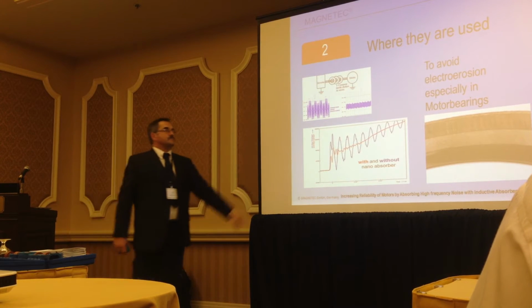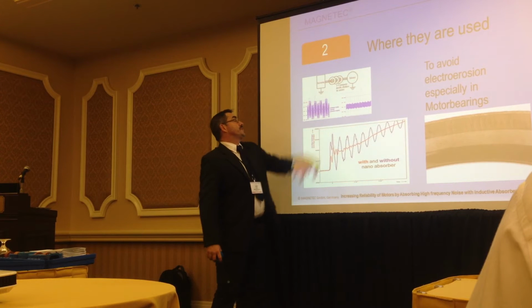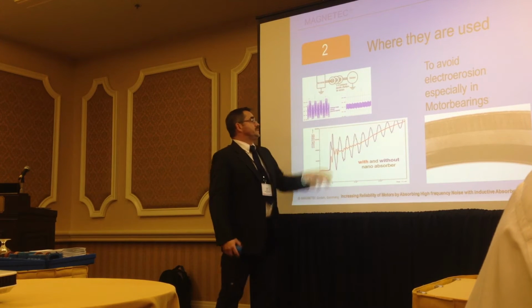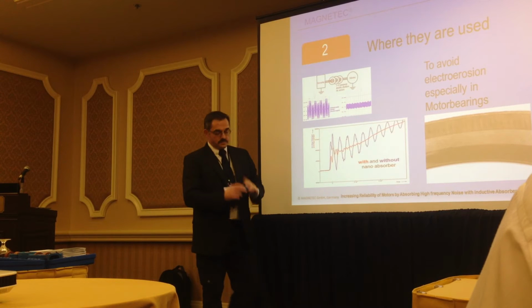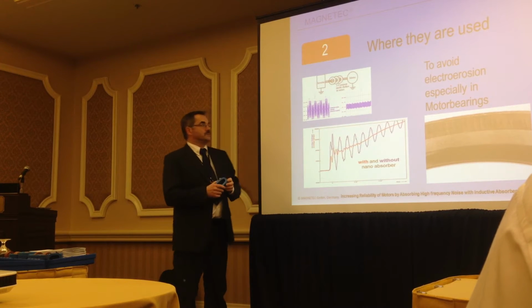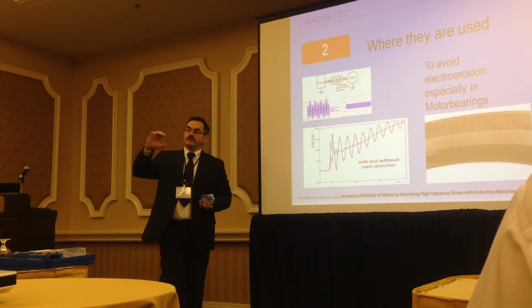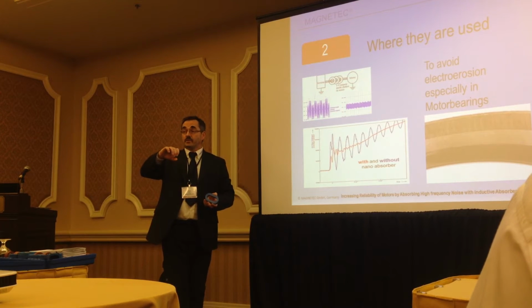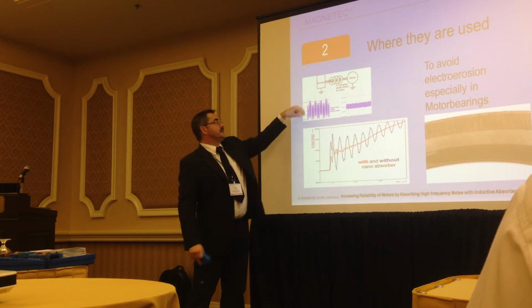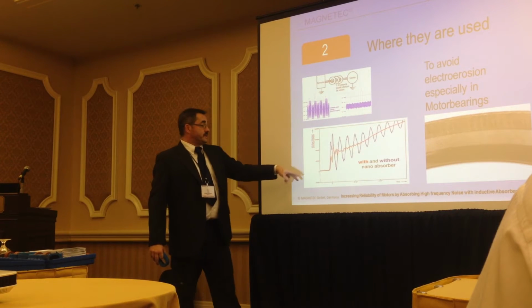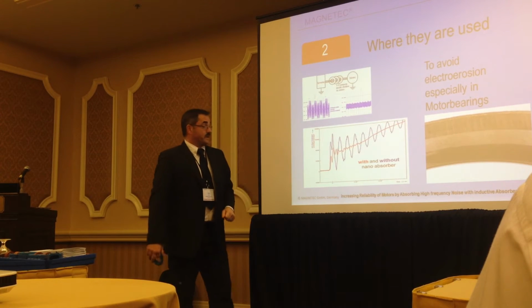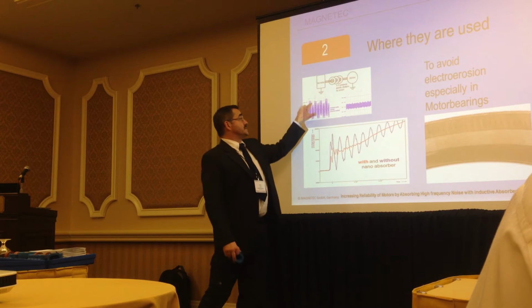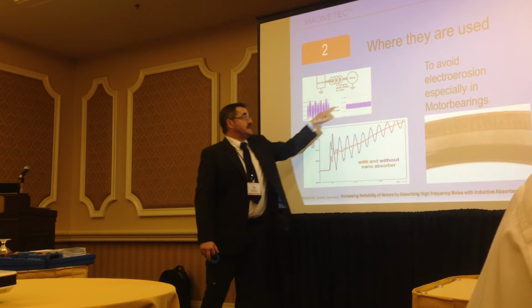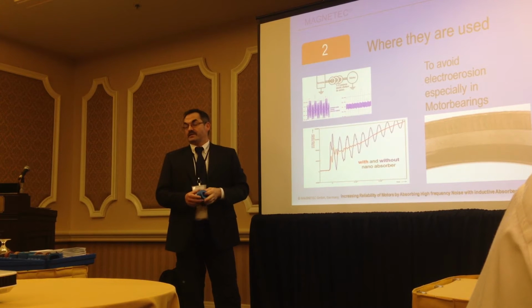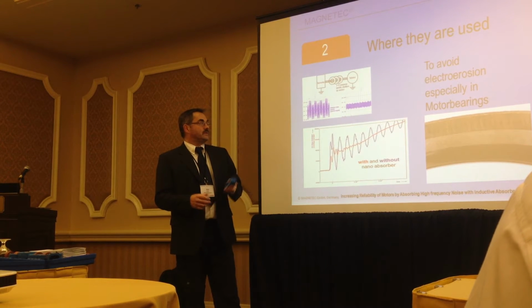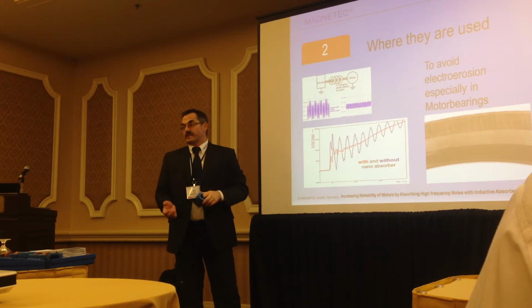For example, here you have an inverter, a variable frequency drive, you have a motor, and you just put these things over the cable. Then you measure the common mode, when you put the clamp over all three lines of the motor and measure the peak current. Here you can see very high frequency noise, and when you put it over, it's really reduced to these undangerous peaks. I'll come to that point later, how to define what is safe and what is unsafe.